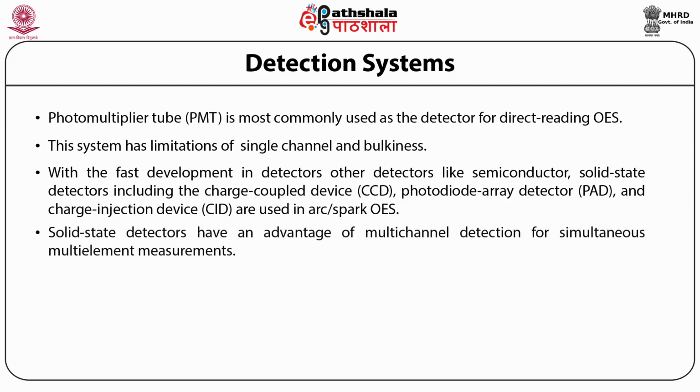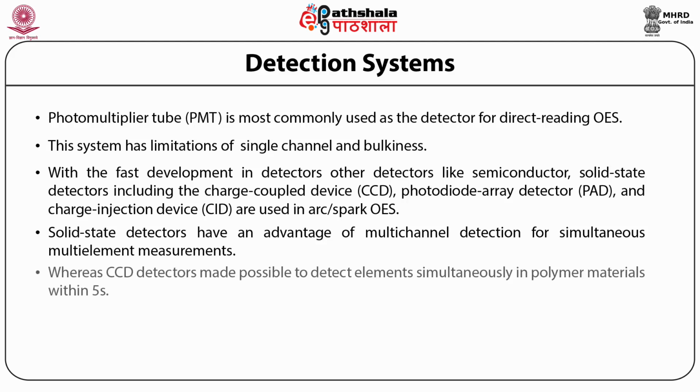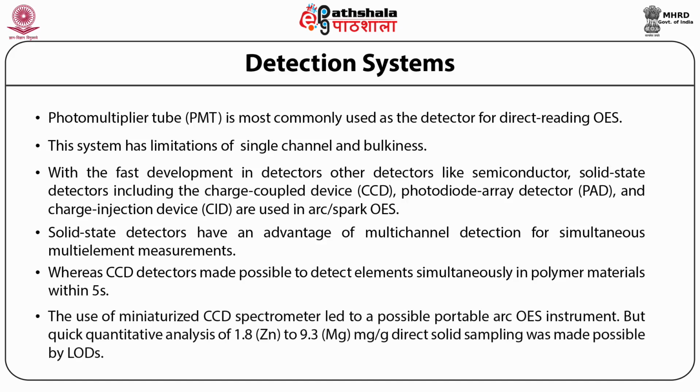The solid-state detectors have the advantage of multi-channel detection for simultaneous multi-element measurements, whereas CCD detectors made it possible to detect elements simultaneously in polymer materials within 5 seconds. The use of a miniaturized CCD spectrometer led to a possible portable arc optical emission spectrometer, and quick quantitative analysis of 1.8 zinc to 9.3 magnesium milligrams per gram by direct solid sampling was made possible by LODs.